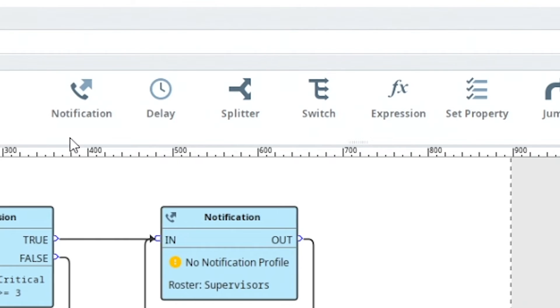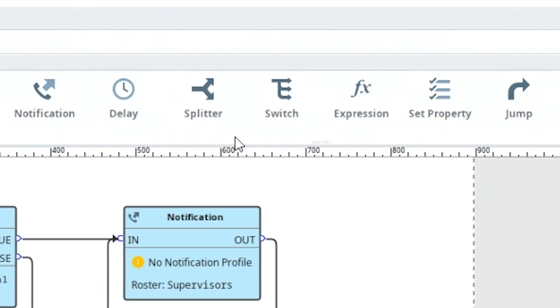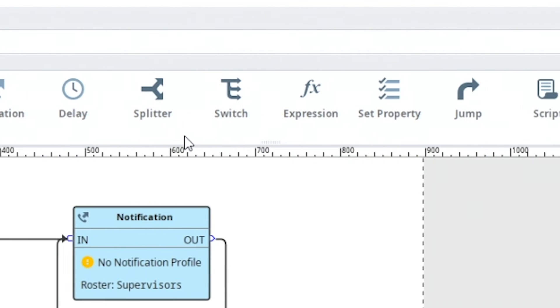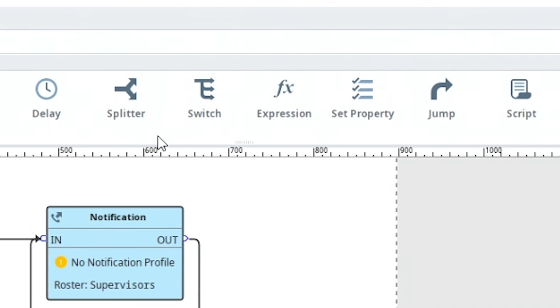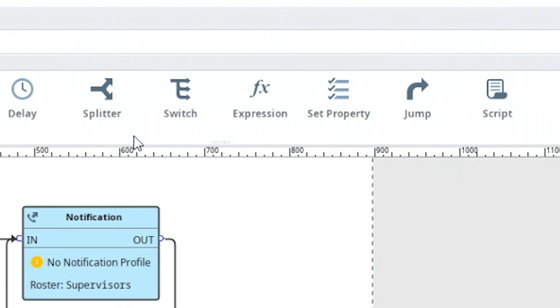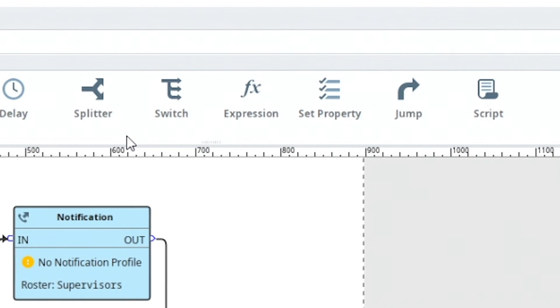There are lots of building blocks to build the logic any way that you want, and these blocks are fundamental to how that logic is handled. You can see all those building blocks right here. There are blocks for notifying people, blocks for waiting or delaying, switch statements, and expression statements to provide your own logic and to do filtering of alarms. There's the ability to jump or escalate to different Alarm Notification Pipelines, and even the ability to specify your own custom logic through Python scripting.